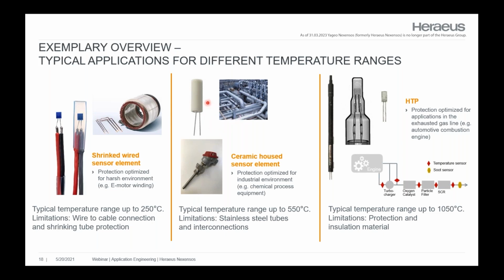Then you can switch to a different housing again, which is a ceramic tube filled with ceramic paste, and you put in our sensor. You have to take care about bubbles and air holes, like Charlotte described before. And if you make everything proper, make a nice connection, you can put it into a probe like that, and you have a good solution which works up to 550 degrees.